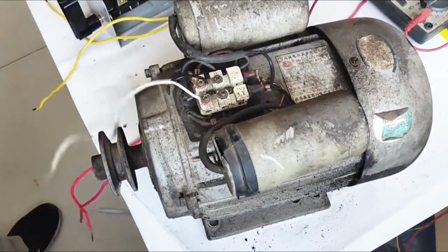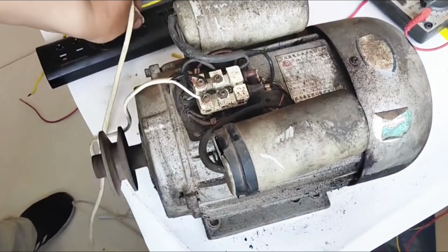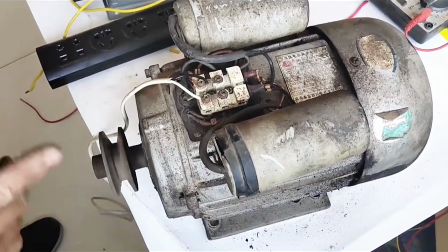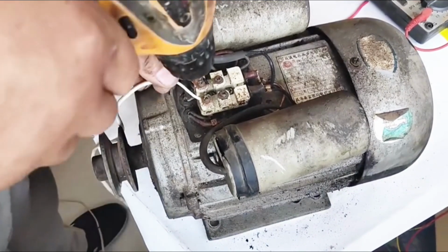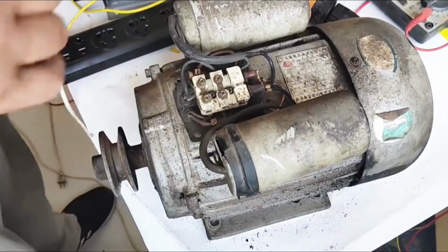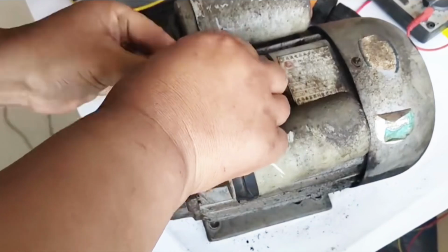Let's take a look at the single capacitor motor forward and reverse schematic diagram. From the diagram we can see that the position of the live wire connection determines whether the motor is forward or reverse. A single capacitor already makes the motor run normally, so why add another run capacitor? This run capacitor plays a compensatory role here.